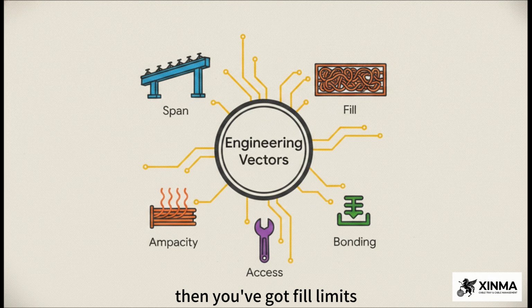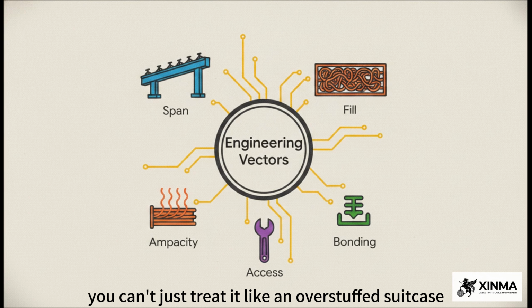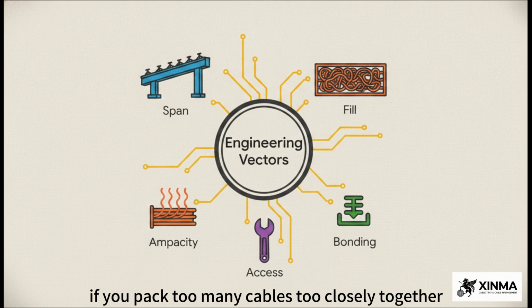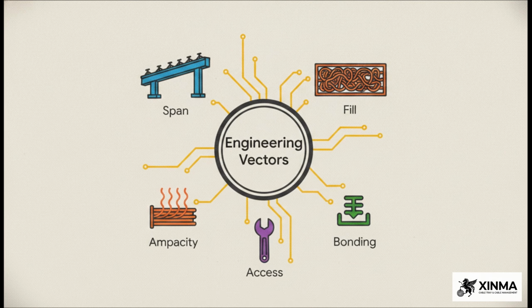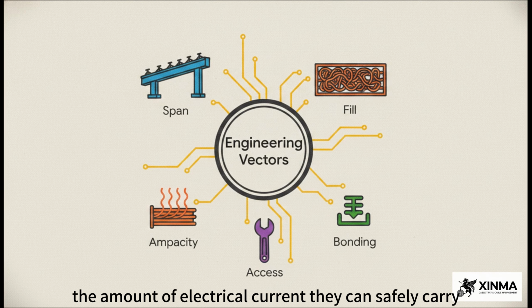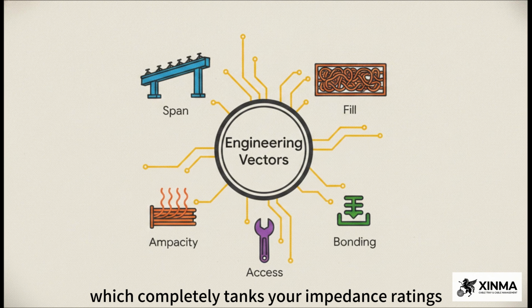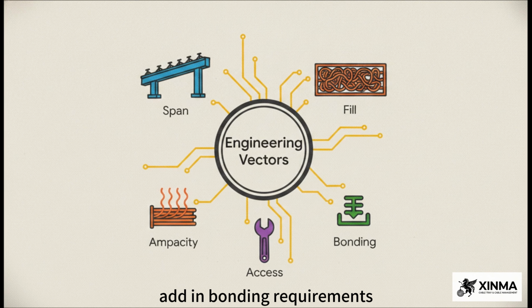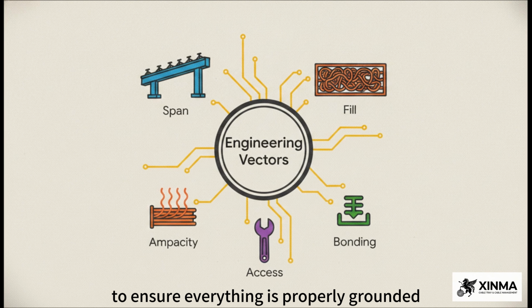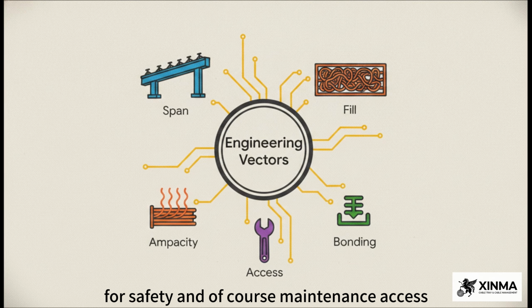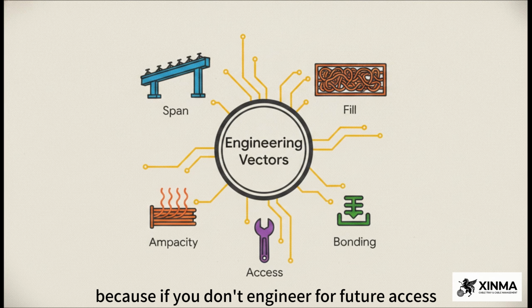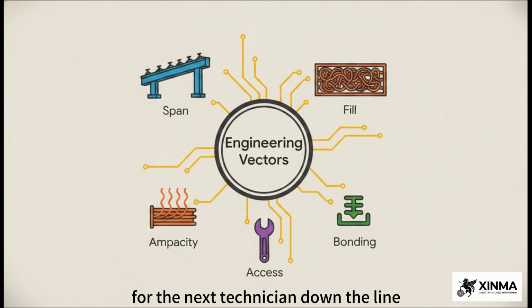Then you've got fill limits. You can't just treat it like an overstuffed suitcase. If you pack too many cables too closely together, they generate heat. That heat restricts the amount of electrical current they can safely carry, which completely tanks your ampacity ratings. Add in bonding requirements to ensure everything is properly grounded for safety, and of course maintenance access. Because if you don't engineer for future access, you're just creating an absolute nightmare for the next technician down the line.